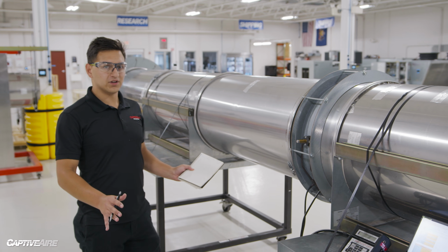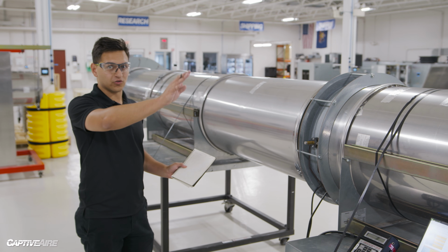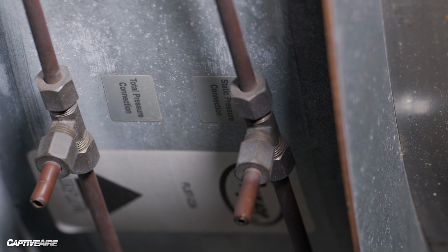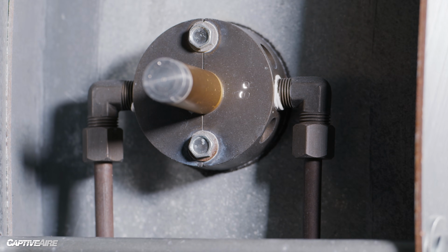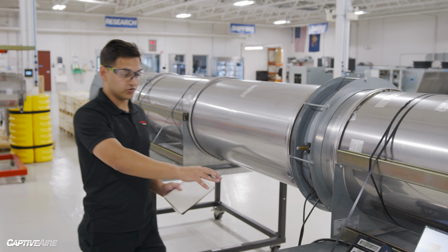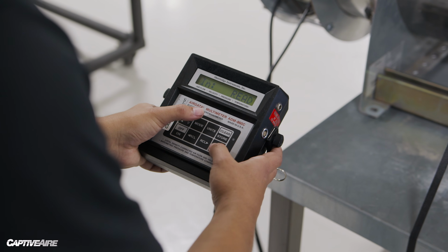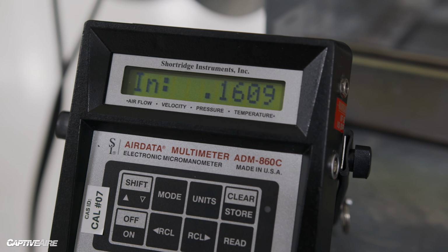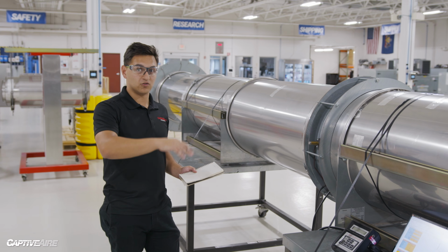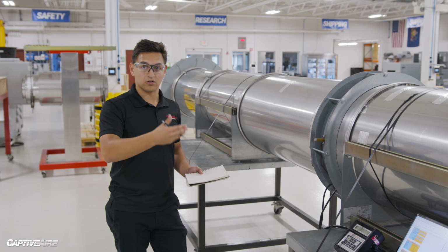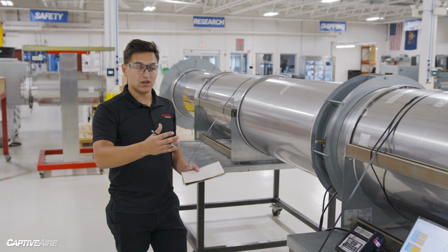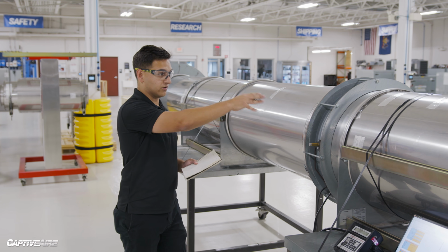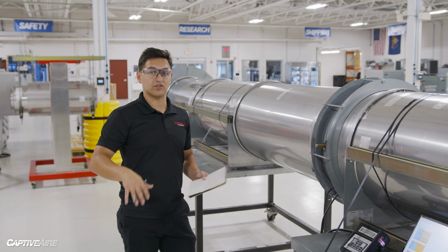So here we see our test rig. We have this long piece of duct attached to our inlet here, and we have 2 points on our duct here. We have a port for total pressure and a port for static pressure. So our Shortridge, which is our pressure reader right here, can take the difference of our static and total pressure, and that gives us dynamic pressure. Once we have dynamic pressure, we can convert that to an airflow or air velocity in feet per minute. And then once we know that, we can multiply that feet per minute by the area of our ductwork, and that gives us our CFM.